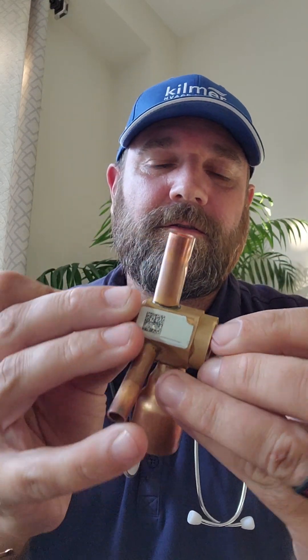Closing force P3 is the superheat spring located there, and that's going to push against the push rod in the valve to act as another closing force. These three forces act together to slide the push rod back and forth, metering different amounts of refrigerant to maintain constant system superheat.